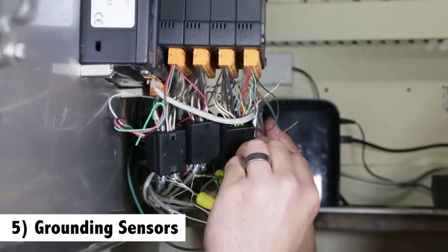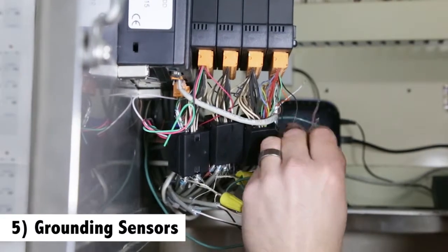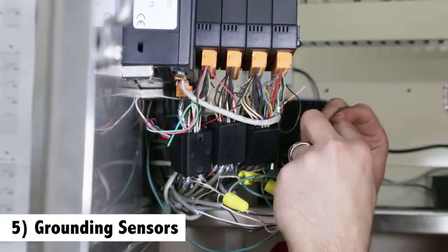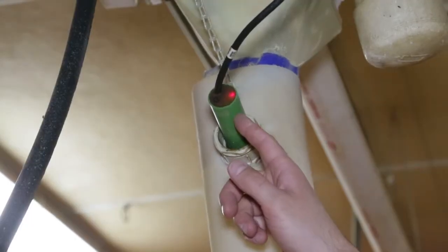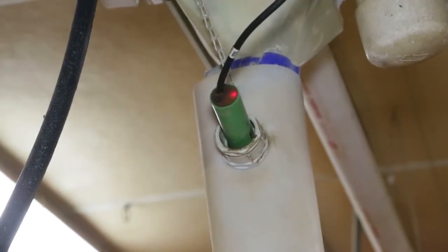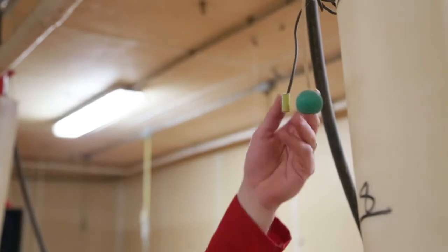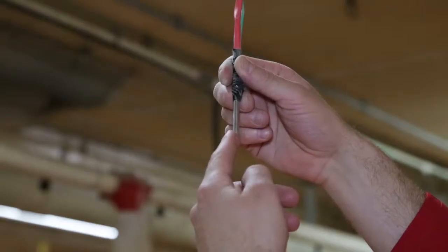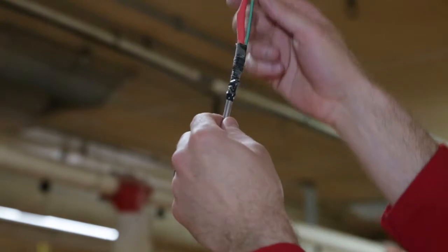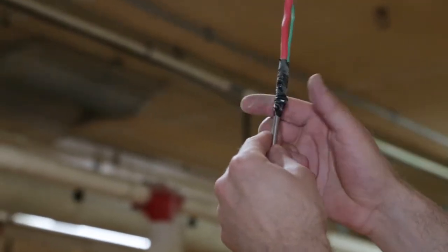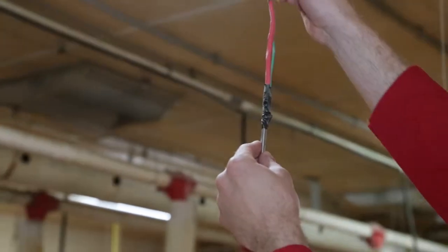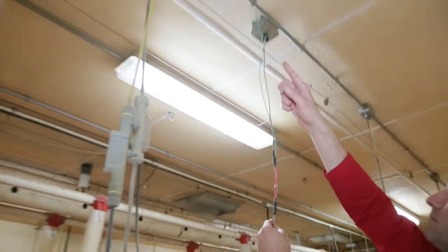It is very important that you ground all equipment. Please be sure to follow these steps carefully. Make sure to ground all equipment in the barn including feed sensors, temperature probes, humidity probes, and alarm probes. Equipment suspended by ropes or hanging on plastic pulleys is typically not grounded. Ungrounded equipment will build a static charge. When touched, the equipment will become discharged.